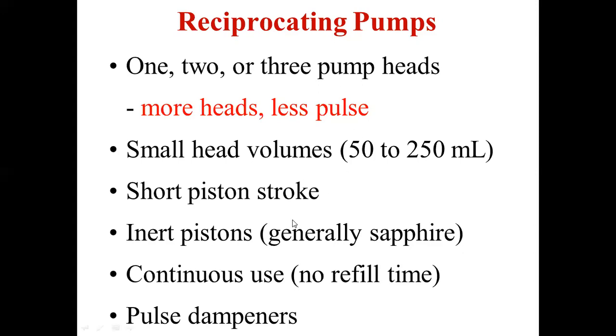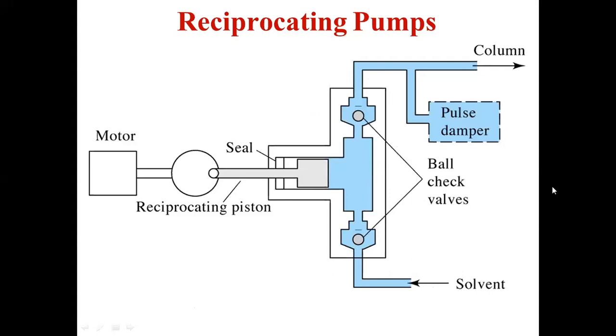And the pistons are going to be inert. We can say inert pistons are going to be used because they are not going to be degraded. So with time, the functioning of the piston will remain intact. There is no modification of the nature of the piston, irrespective of the material used, and it can be used continuously. Because it will be connected to the sample reservoirs, we need not refill the liquids during the separation process, and it can be fitted with pulse dampeners very easily. Therefore, these pumps are very advantageous.